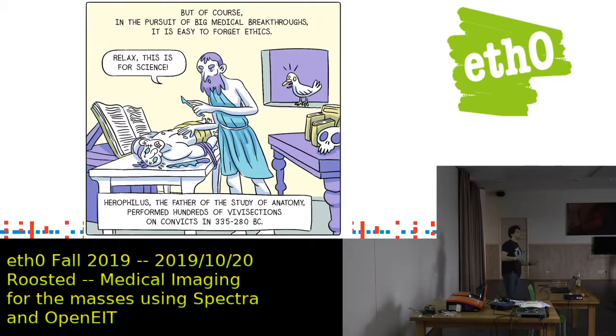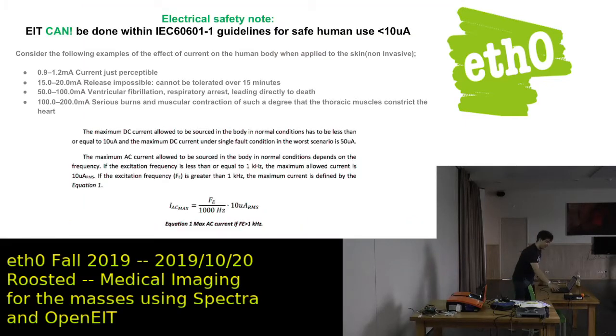But first, since I'm going to introduce it to you as a hacking tool, I should first make sure that it's actually safe to use and safe to hack with. I participate in a lot of studies, and I do a lot of medical research things. It's sometimes really easy to go into the gray area of what is healthy for you and what is not. But luckily, the Spectra complies with the IEC 60601 guidelines because it uses very, very little current. To measure impedances, it puts out a very small current between two electrodes and measures the voltage between them. The first currents usually feelable are around the 1 milliamp mark, and this is a couple of factors lower because it will never produce currents of more than 10 microamps.